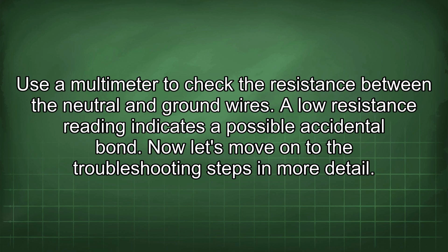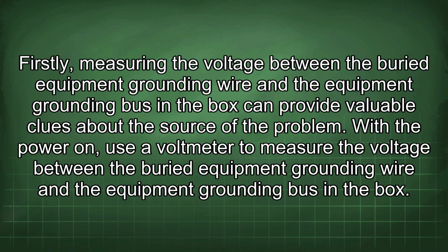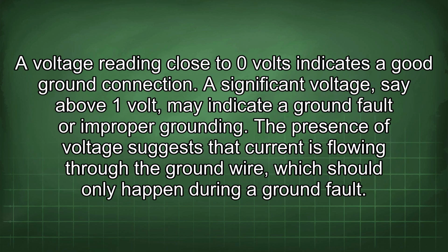Now let's move on to the troubleshooting steps in more detail. Firstly, measuring the voltage between the buried equipment grounding wire and the equipment grounding bus in the box can provide valuable clues about the source of the problem. With the power on, use a voltmeter to measure the voltage between the buried equipment grounding wire and the equipment grounding bus in the box. A voltage reading close to 0 volts indicates a good ground connection. A significant voltage, say above 1 volt, may indicate a ground fault or improper grounding.